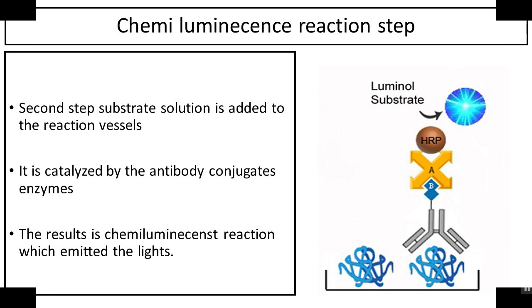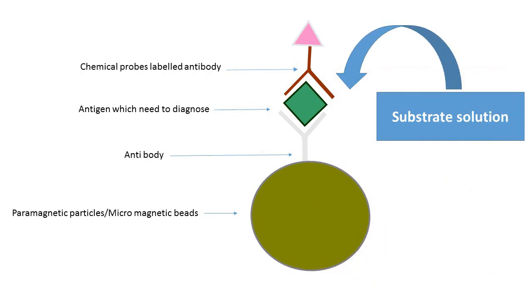In the second step, substrate solution is added to the reaction vessels. It is catalyzed by the antibody conjugate enzymes, resulting in a chemiluminescence reaction.